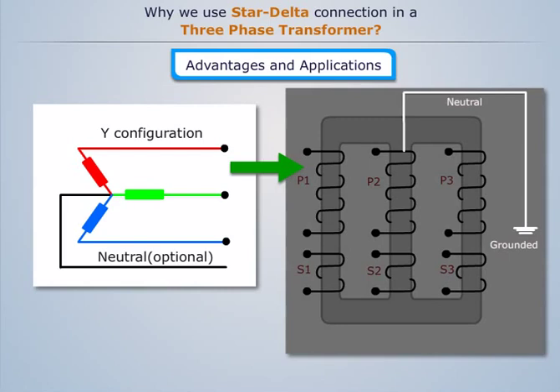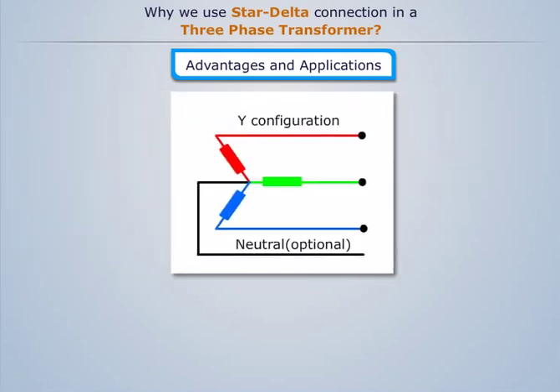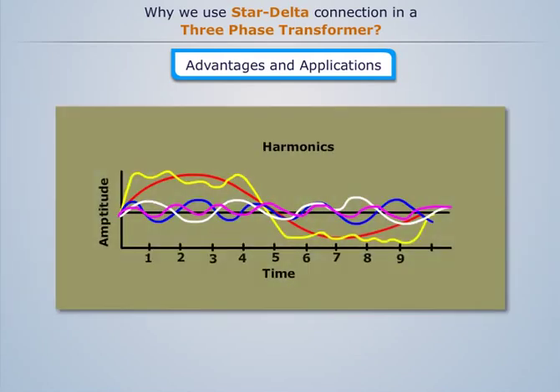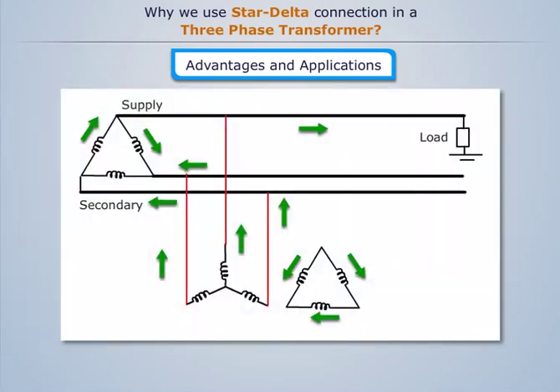Large unbalanced loads can be handled satisfactorily. The YD connection has no problem with third harmonic components due to circulating currents. As a grounding transformer in power systems, mostly grounded Y-Delta transformer is used for no other purpose than to provide a good ground source in ungrounded Delta systems.